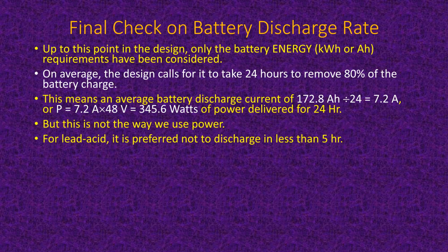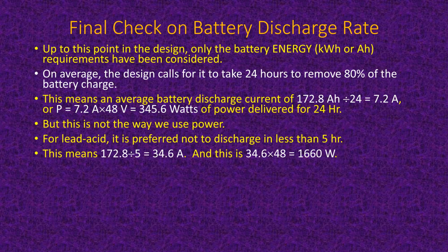Now, for lead acid, it's nice if you can limit your discharge to taking more than 5 hours. Because if you discharge in less than 5, you lose quite a bit in terms of heating the inside of the battery and not being able to use it to heat your coffee in the microwave oven. So if we want to discharge them in 5 hours, we can pull up to 34.6 amps. So that's 1,660 watts, and 1,660 watts will run a lot of appliances.